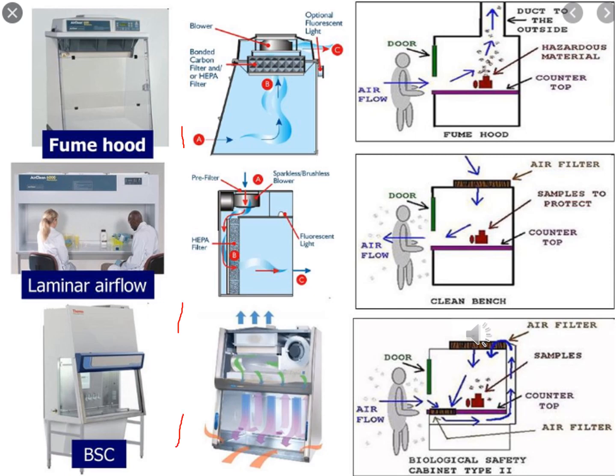Here you can see how they look. This is the biosafety cabinet, the laminar flow, and the fume hood. On this side, for instance, this is the worker and this is the fume hood, and you can see the airflow is from here. The air enters from here because this is the glass door. There is a glass door in each cabinet, whether it is a biosafety cabinet or laminar flow. This glass door is sliding, so you can adjust the height of the glass door according to the height of the worker.